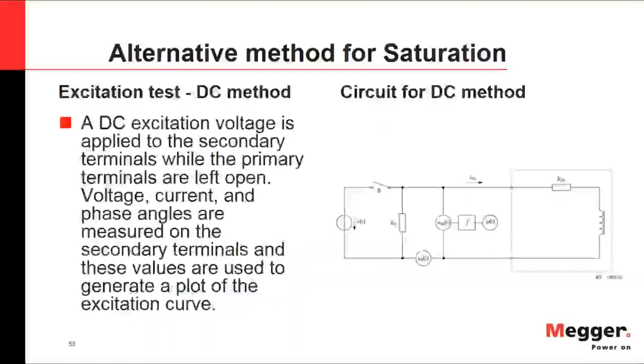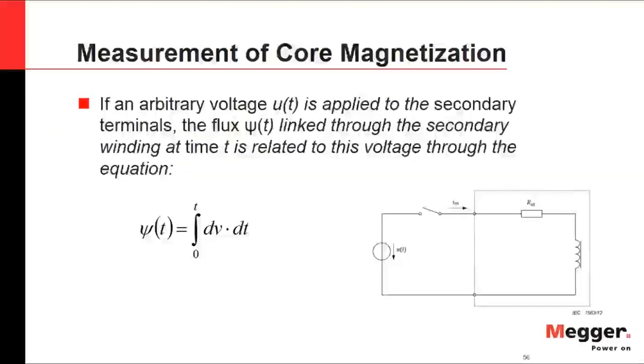For this DC alternative saturation method, by applying a DC signal we integrate the voltage as a function of time, which is reflected as flux as a function of time. We then look at the saturation curve as voltage-time versus excitation current. An arbitrary voltage is applied to the secondary terminals, and the flux linkage through the secondary winding at time t is related to this applied voltage according to the governing equation.